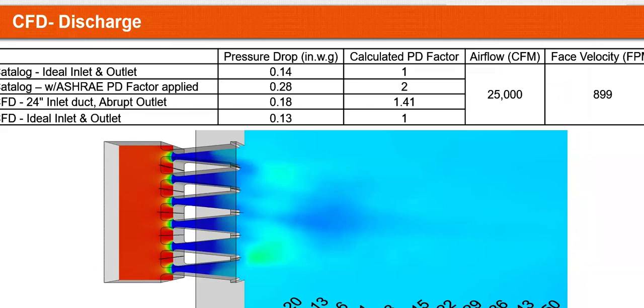We did the CFD analysis as well. As a minimum, you need this. This is the top of the chiller, just so that you guys know. It's just tilted sideways on this specific analysis when we were looking at the back pressure created by putting silencers too close to the fan. So the orange is the back pressure that we create on that plenum, and it's the amount of pressure the fans are going to have to overcome to push the air out. So using the right silencer with the lowest pressure drop, a very specific distance away, which for a discharge side on a chiller is at least 2 feet of distance between the silencers and the fans, can ensure that you have acceptable pressure drop levels as per manufacturer of the chiller recommendations.